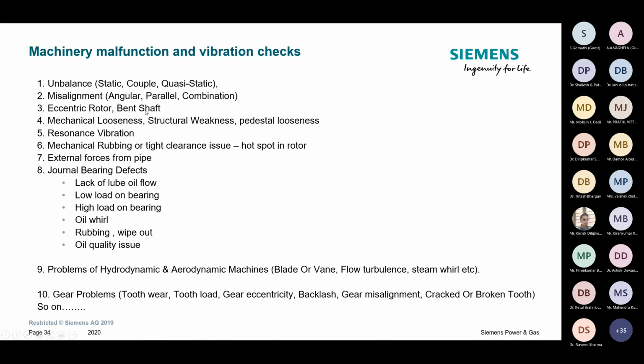Eccentric rotor or bent shaft is another reason. This can happen in two ways. One is when the rotor starts heating up, because it's subjected to 540, 560 degrees Celsius. Thermal expansion is uneven in the system. If soaking is not properly done, then the shaft will bend by certain amounts, 0.2, 0.3. Eccentricity will be 0.6, 0.8. So this nominal 0.6, 0.8 mm also creates high vibration in the system because it's a huge mass.